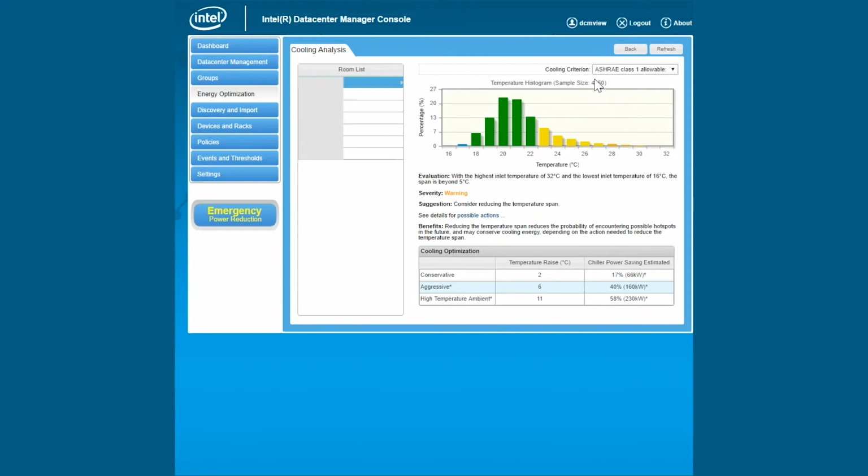So, first of all, in this data center we have 4,050 devices that have temperature sensors that we can read. So actually we have 4,000 temperature sensors in this room. And here we have a histogram that represents how many devices are sensing every temperature. So for example, I have 883 devices that are sensing 21 degrees Celsius in the front panel. And I have only 197 devices that are sensing 24 degrees in the front panel. And I have just a very small amount, maybe 51 devices, that are sensing 27 degrees in the front panel. I will explain what we see.